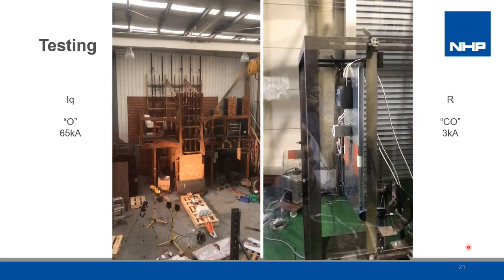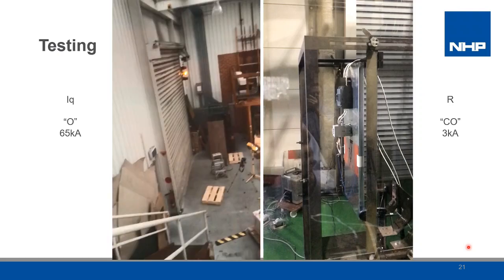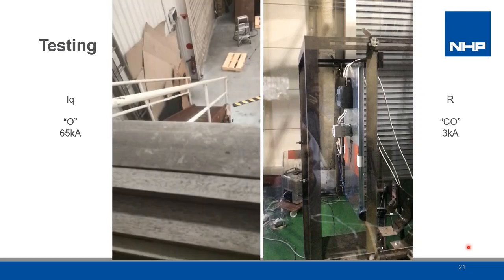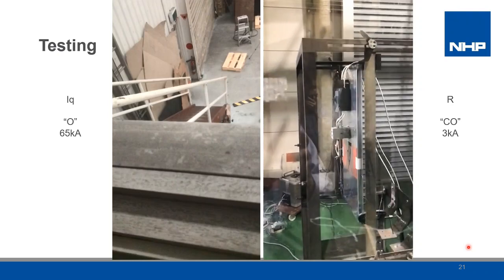To help understanding of what is involved in the testing, we have a couple of videos taken during testing for you to consider. First off, a 65 kA short circuit. And the shock wave of the short circuit opening actually caused the camera to move. The second unit was a contactor closing onto a fault level of 3 kA. As this all happens in milliseconds, it doesn't really look too spectacular.